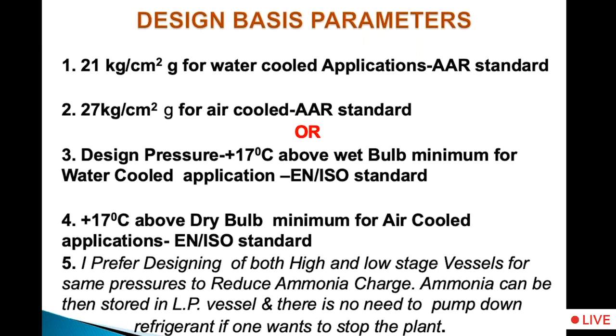These pressures are different because whatever standards I showed you earlier are based on European conditions where the ambient conditions are low. So their design pressures are different. In India, being a tropical country, our ambient temperatures go as high as 40 degrees centigrade, whereas their design standards are all for 35 degrees centigrade maximum dry bulb temperature. So we have considered these higher pressures, and therefore our systems will become safer.